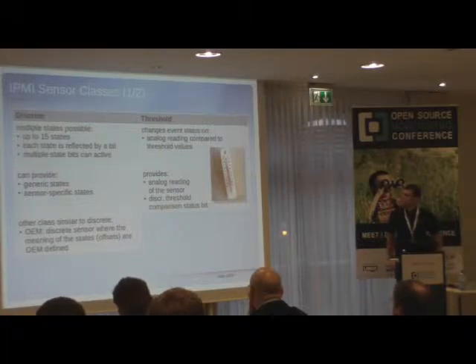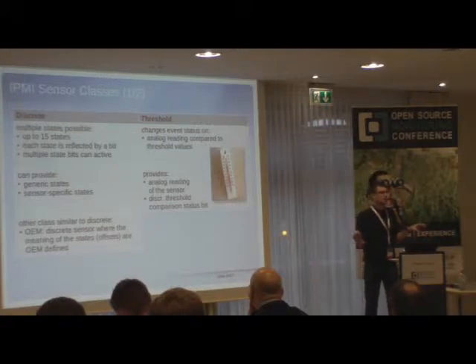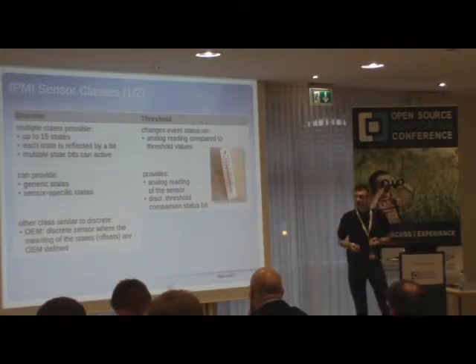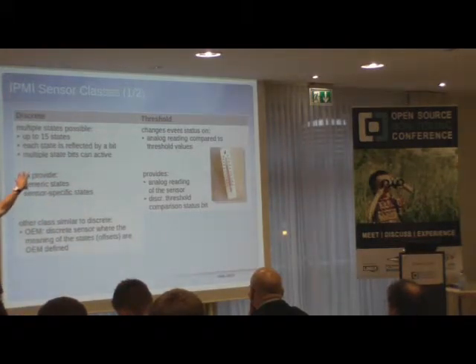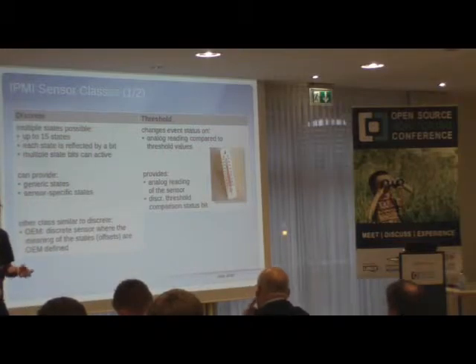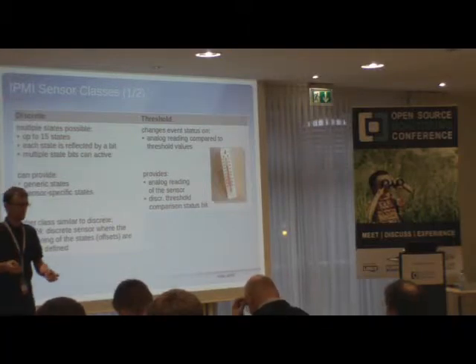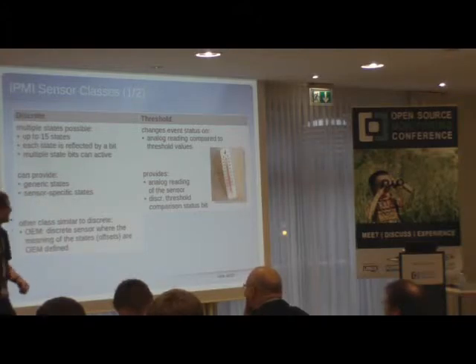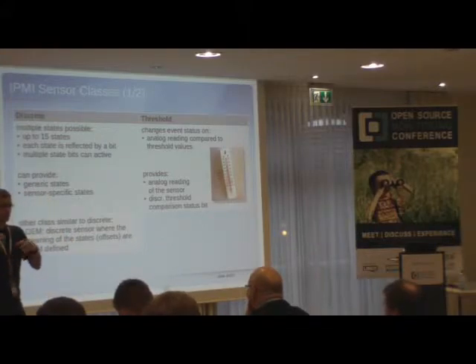When we talk about IPMI sensors, there are two types of sensor classes within IPMI. On one side you have the discrete sensors, which have the possibility to use up to 15 different yes-or-no states. This is very convenient, for example, for a power supply — you don't get a numeric value, but rather: the power supply is present, it has power on the inlet, it is working correctly. So you have up to 15 different states which you can use.